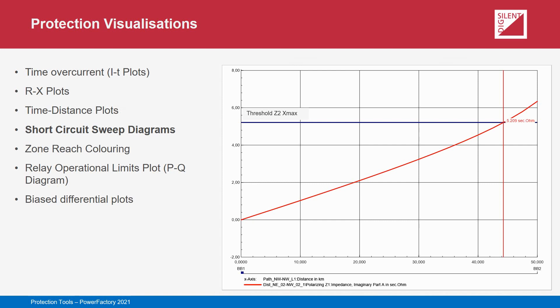Any variable of any element can be observed — for example, the variation in current flow in a particular transformer winding, or the angle between the polarizing voltage and operating current of a directional relay element, or the reactance of a fault loop measured by a relay. Configurable thresholds can also be added to the plot. Common short circuit sweep diagram configurations used for protection purposes can be easily created using the Protection Graphic Assistant tool.